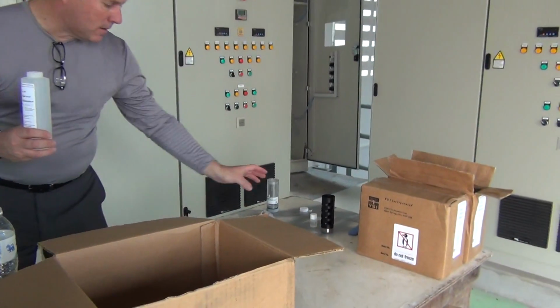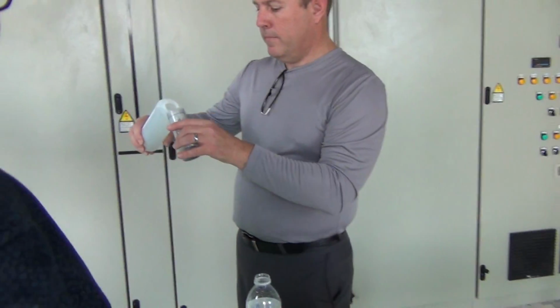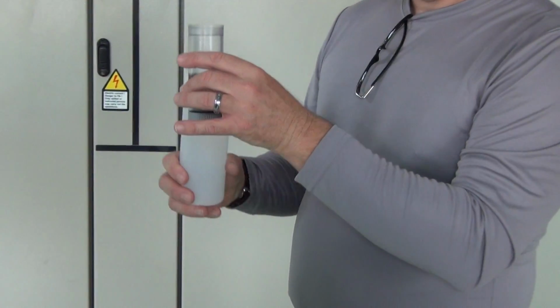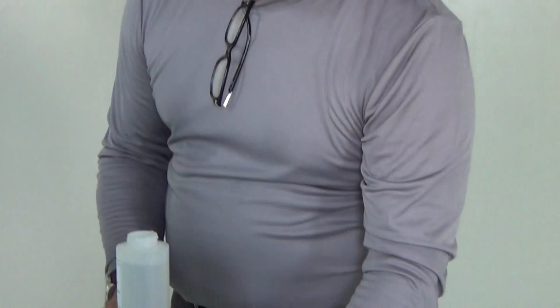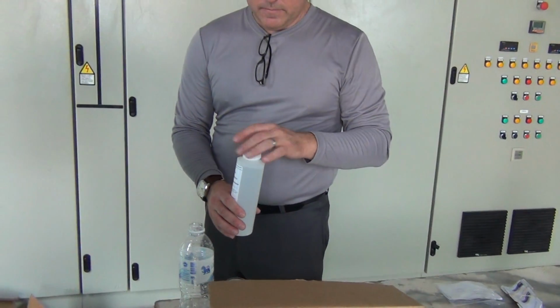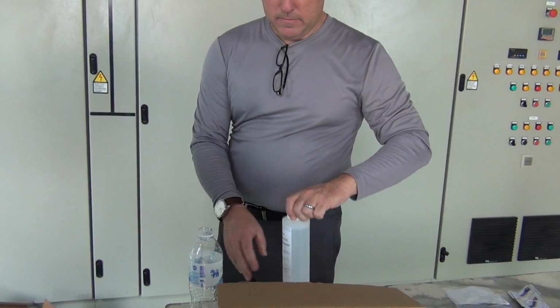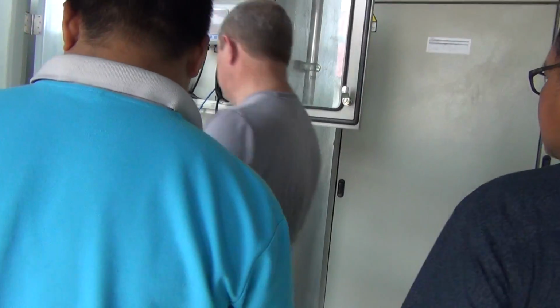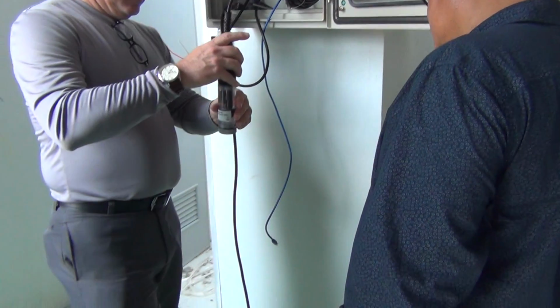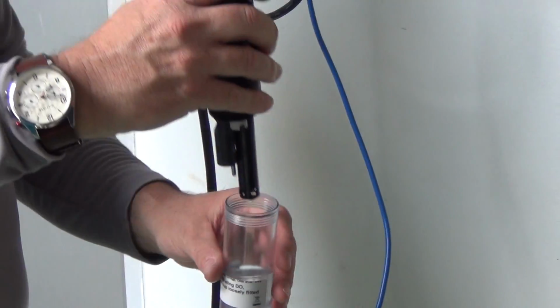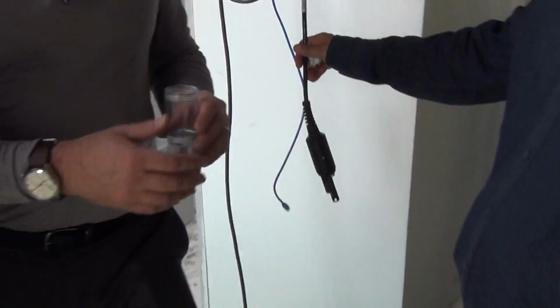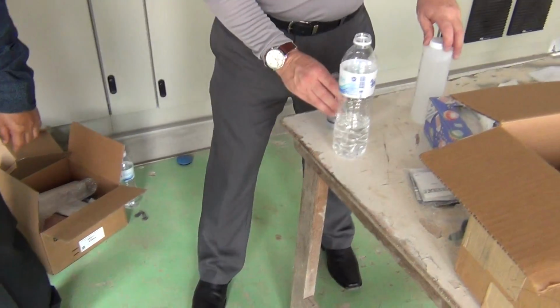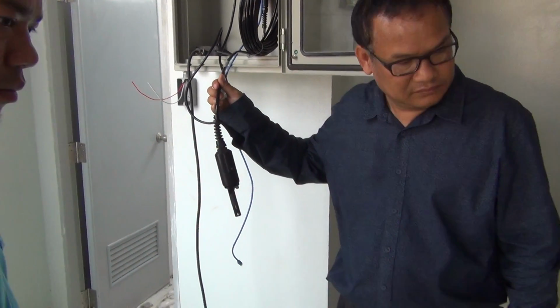Now, this one, we're going to take our cup, I'll put the cup over here, and we're going to fill it to the top of the label. And that's not going to be enough. I need to put more in. We're going to go much higher than the top of the label. We have to fully submerge the probe up until that opening to have an accurate calibration.